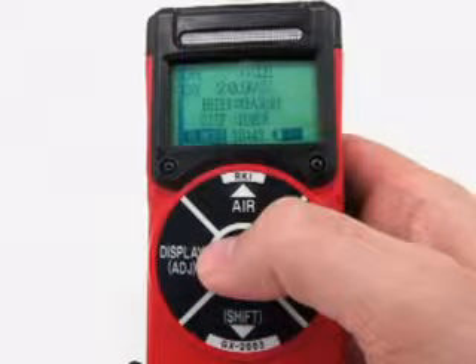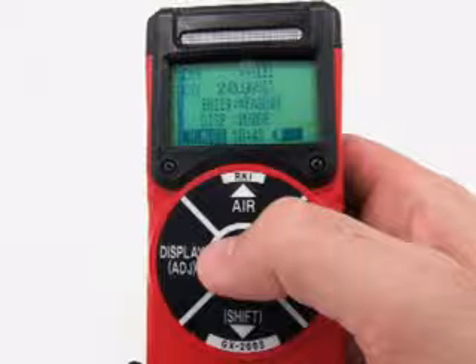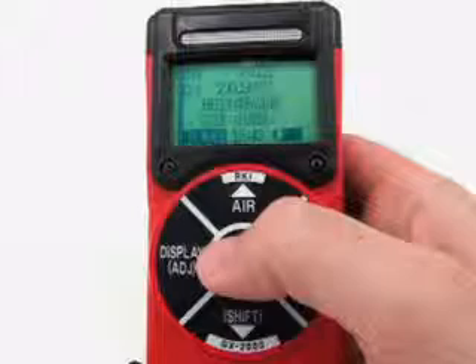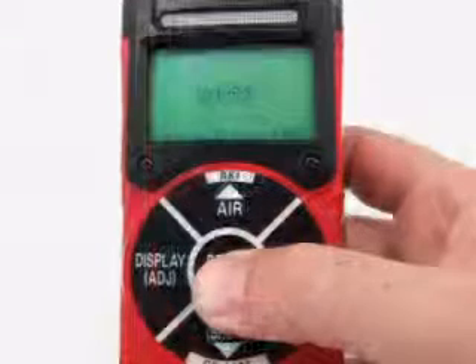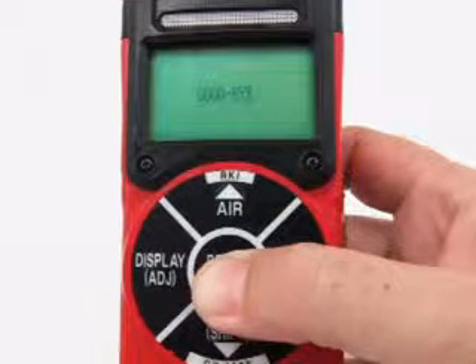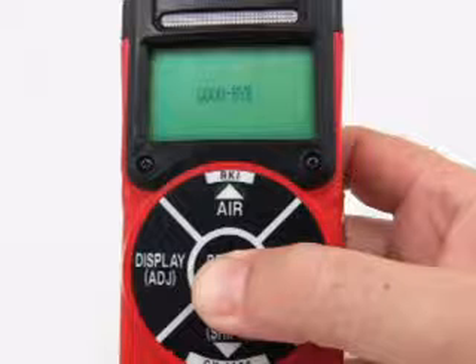To turn off the GX2003 when in the bar hole mode, press and hold the power enter button. The unit will initiate a bar hole measurement. Keep holding the power enter button. The buzzer will sound and the LCD backlight will flash for about 5 seconds. Release the button when goodbye appears on the display. When goodbye disappears and the backlight turns off, the unit is off.